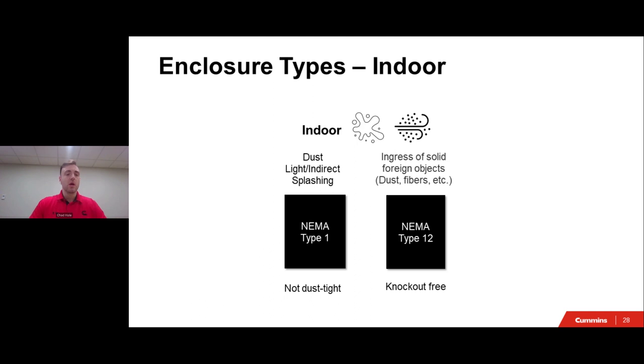Type 12 enclosures provide a degree of protection of the equipment inside the enclosure against ingress of solid foreign objects, those solid foreign objects being falling dirt, circulating dust, lint, and other fibers. The Type 12 also provides a degree of protection with respect to harmful effects on equipment due to the ingress of water, so dripping and light splashing. Gasketed door seals seal the enclosure's contents from airborne contamination in non-pressurized water and oil.